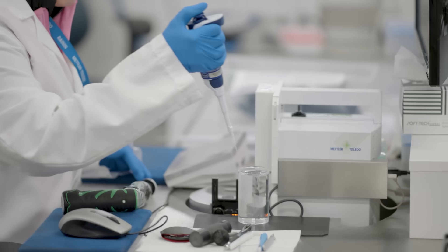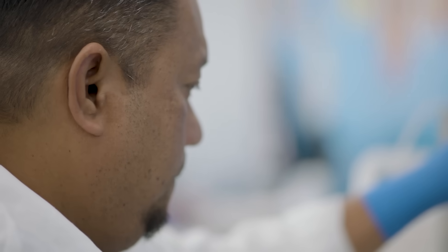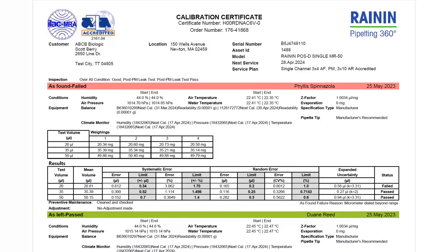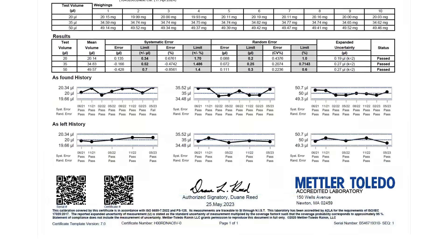All calibrations are guided and securely recorded by our global calibration software, GPSS. GPSS connects directly to Mettler Toledo analytical balances at every station. Around the world, every measurement instantly registers in GPSS, so you can be confident that all data is true and has not been altered. The resulting calibration certificates are compliant and audit-ready, showing results, lab conditions, and testing methods.